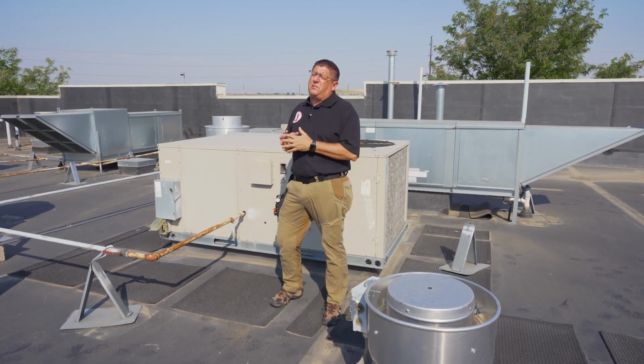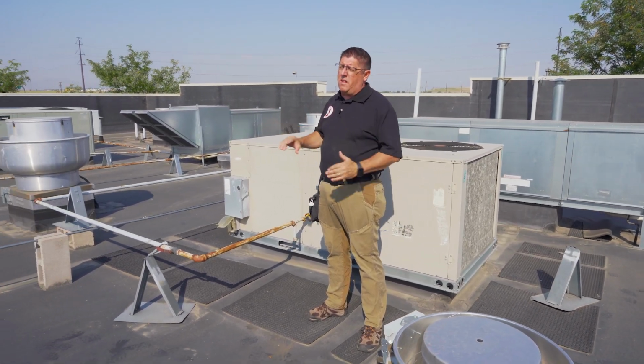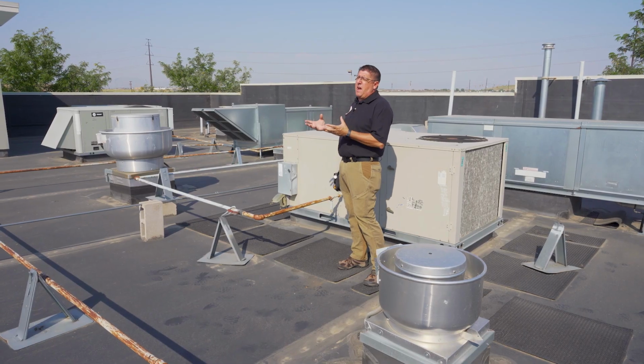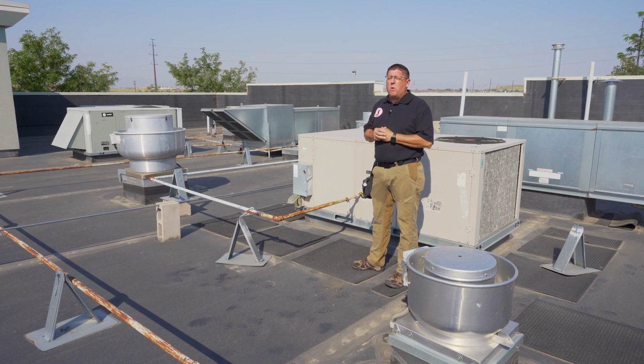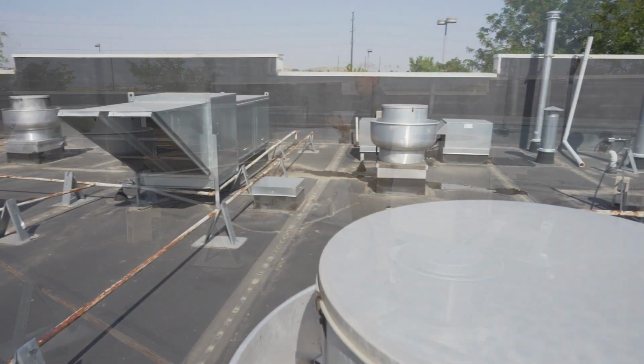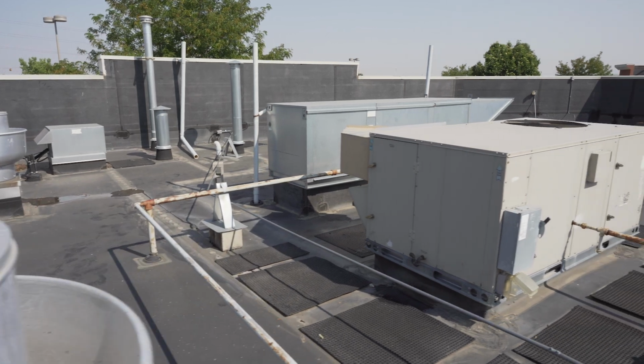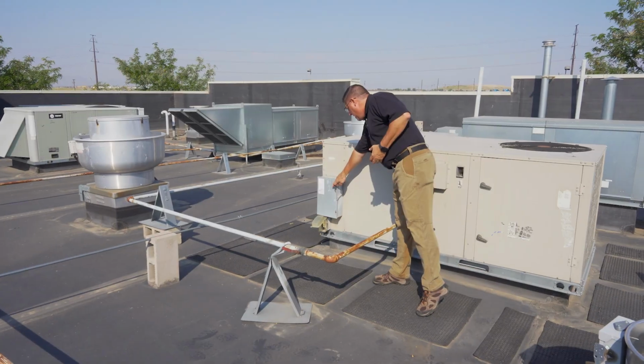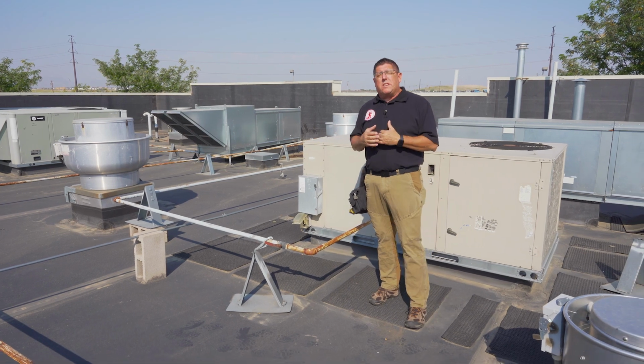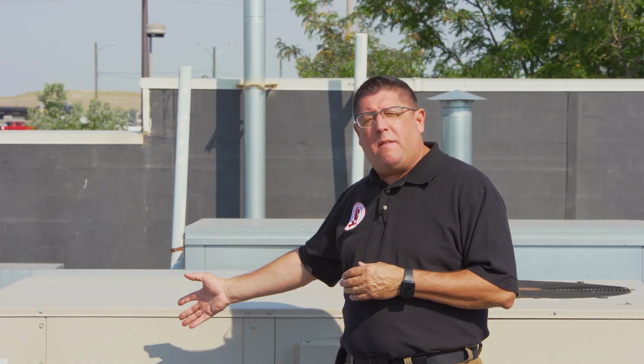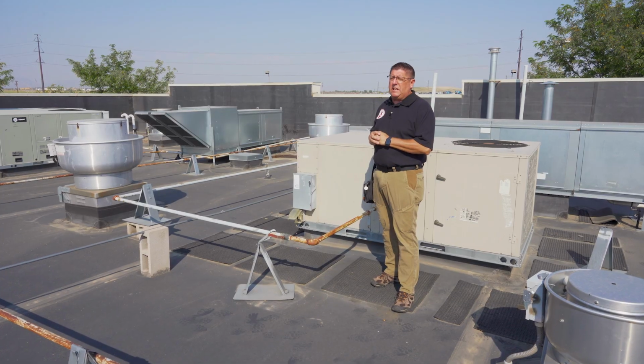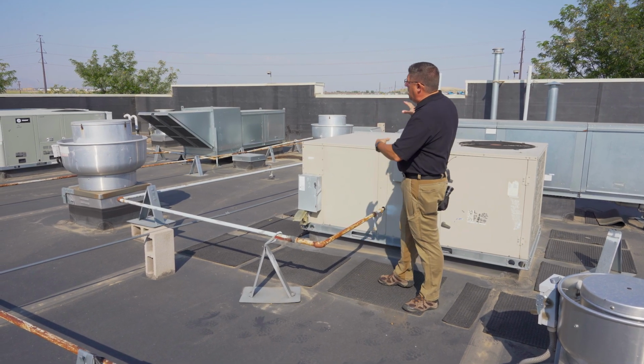When multiple appliances are located up on a roof or anywhere in the property, it's very difficult to know which appliance is for which unit, whether it's a multifamily or, in this case, a commercial setting where I've got 4 large heating appliances up here. In this particular case, this one's actually labeled, it says number 1, and then on the bottom of it's 2. I don't know what that goes to, but I'm hoping that I'll find a thermostat that mirrors that. If I don't, I need to at least identify it on my report to call this unit number 1, 2. And then there might be another unit outside of this that'll have a different labeling on it, but that's very important to identify.